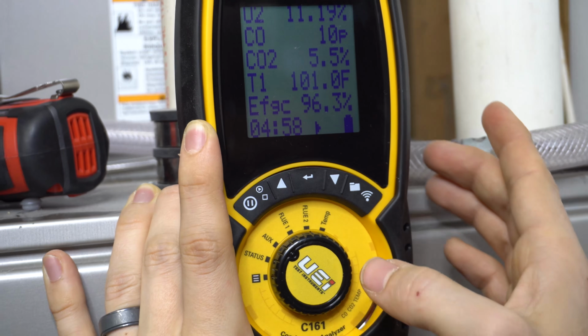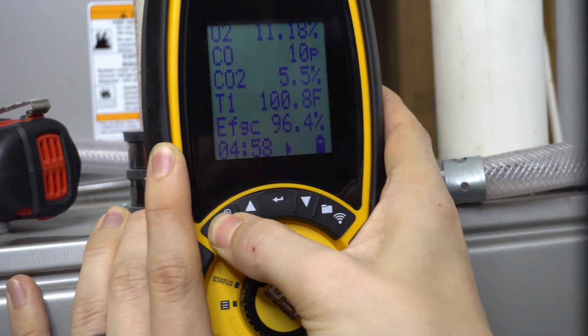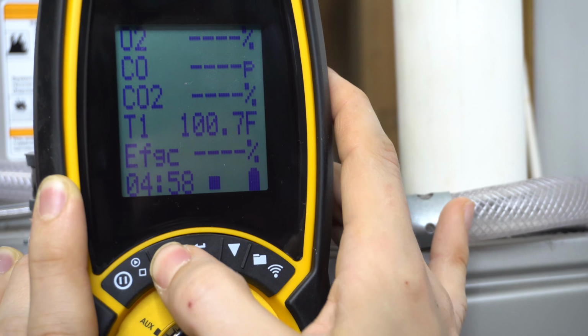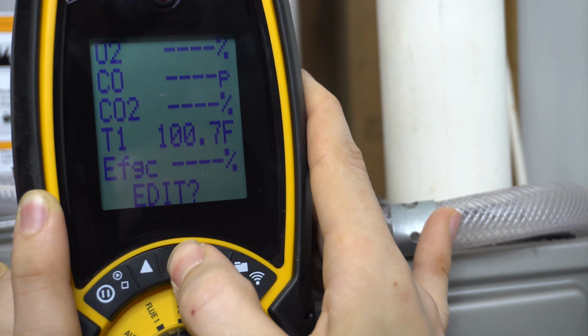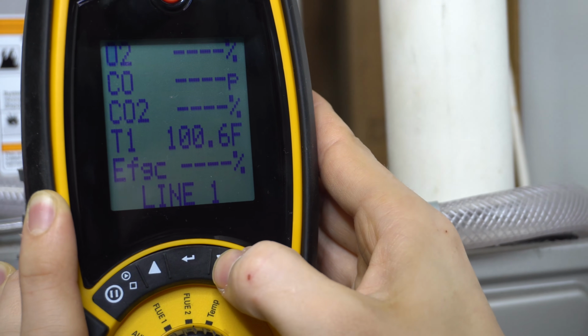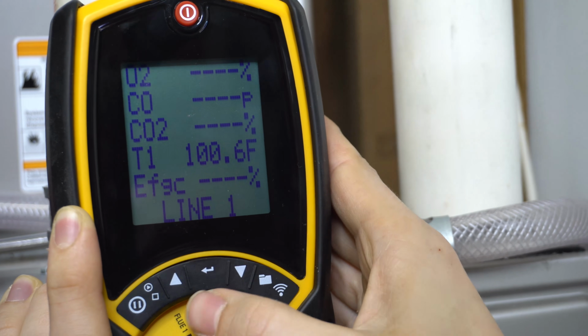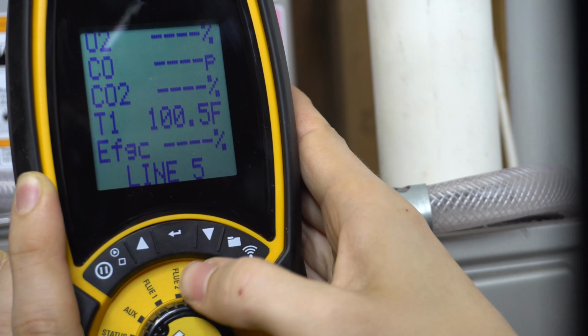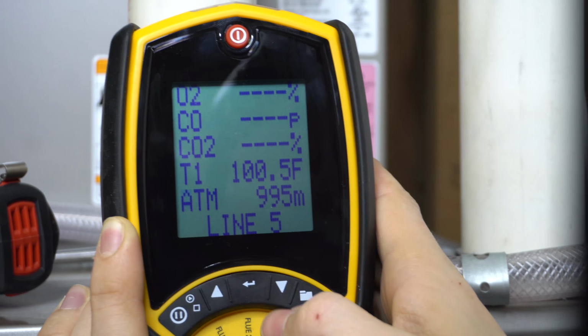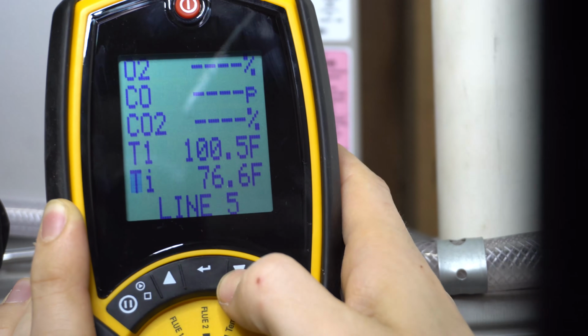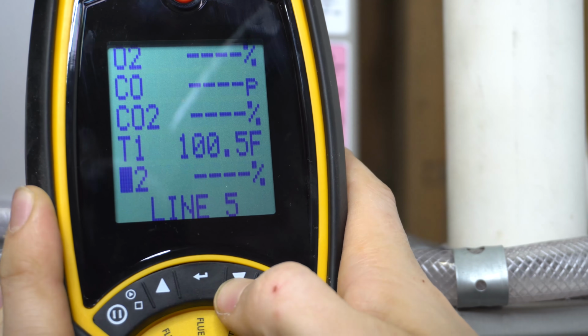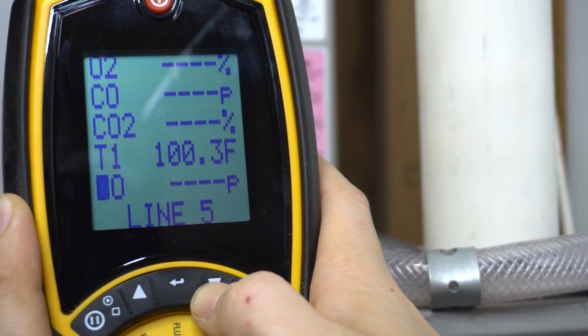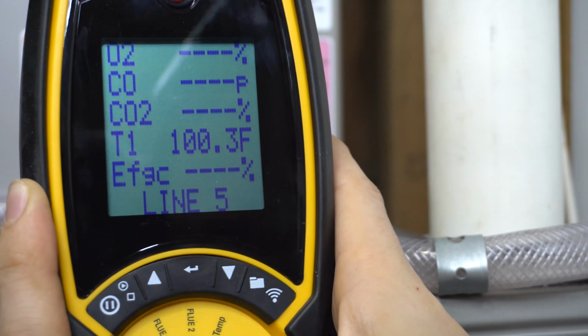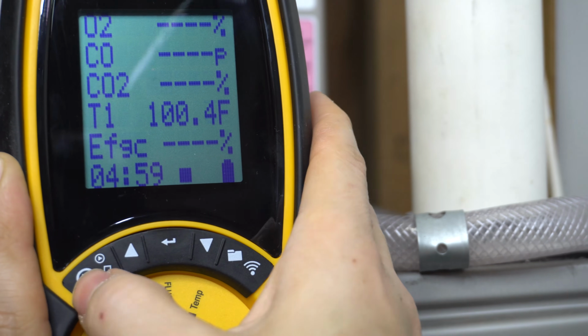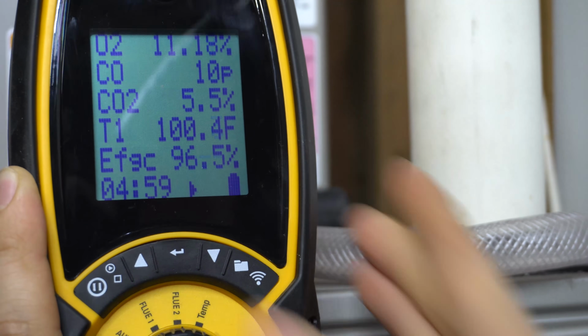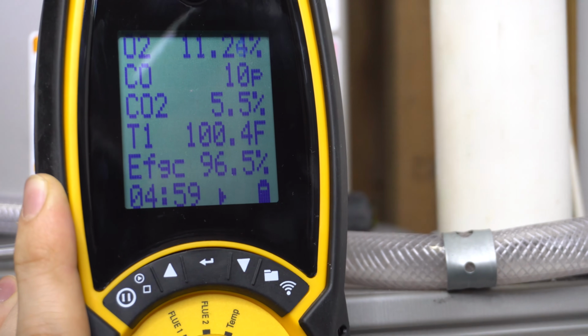And while we're waiting for the furnace to kick into high stage, I just want to show you quickly how I change that. So I pause it, and then if you scroll up until you see edit, you press and hold the middle button, and you're able to edit any of these lines and get whatever value you want. For example, this is the line I switched right here. If I scroll up or down, I can pick whatever I want: the atmospheric pressure, the ambient temperature, temperature 2, temperature 1, oxygen, and so on. But in my case, I want the efficiency, so let's find that again. There it is. Press the center button, and voila. And then we can resume our pump. And we're back in business. And once again, still waiting for the furnace to kick into high stage.